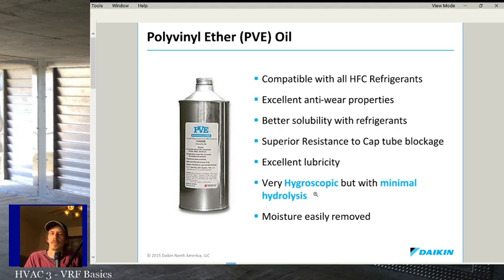It's still going to be a problem though, right? You're going to have moisture in the system, and that moisture is going to create problems being in the system. The thing is, with PVE oil, that moisture is relatively easy to remove. It's going to take longer to remove it during a vacuum than it normally would, because that moisture gets in the system and it stays in there. But it can be removed under a vacuum. With a POE oil, with the regular POE oil, basically once that moisture's in there, it's almost impossible to get out.